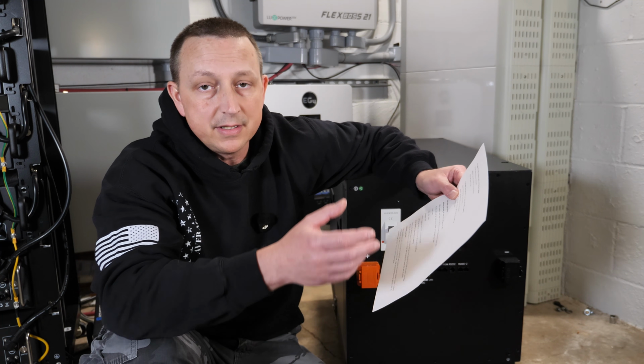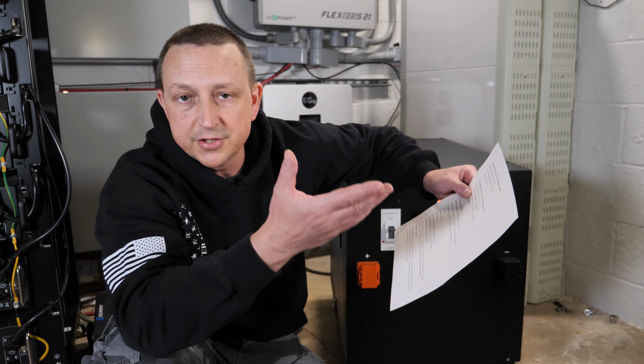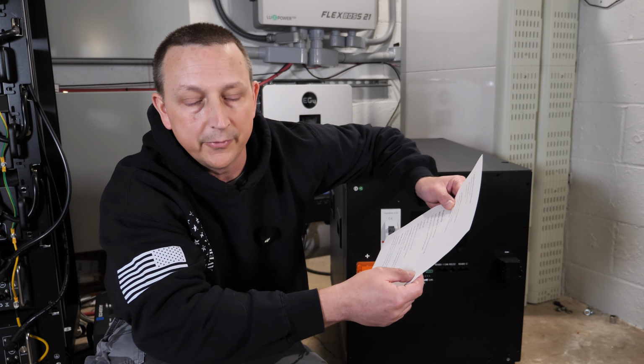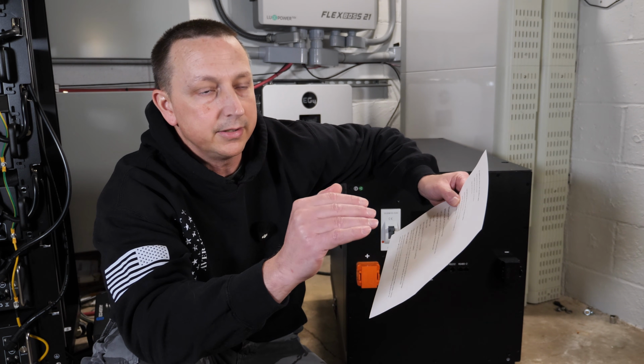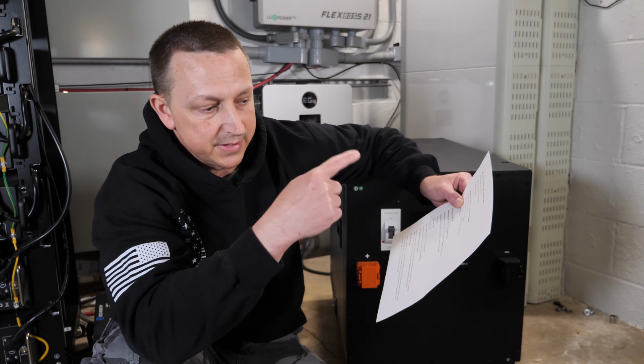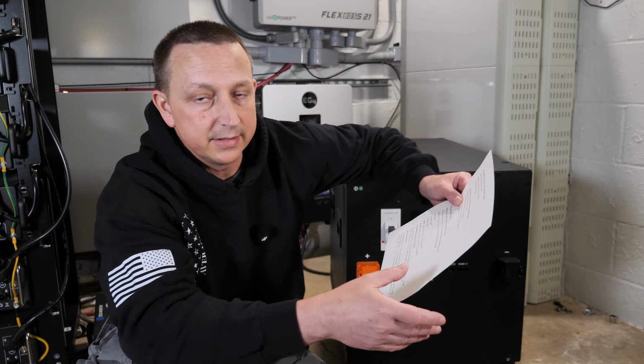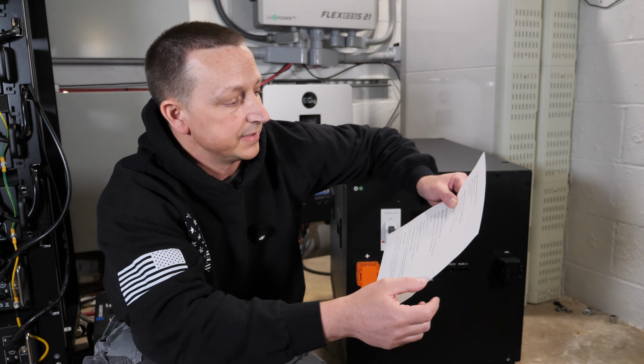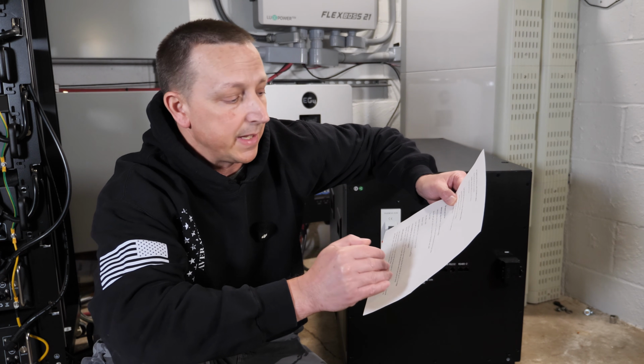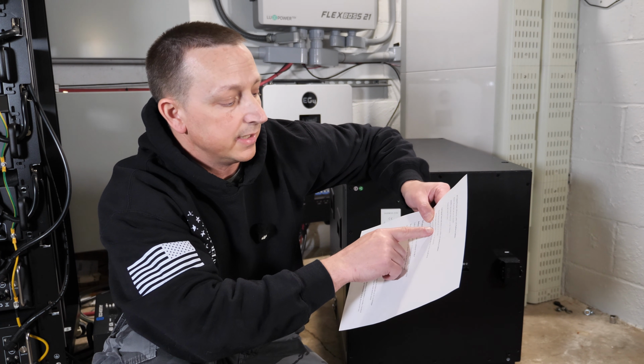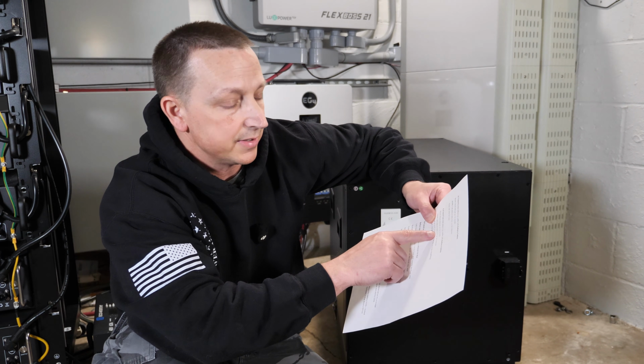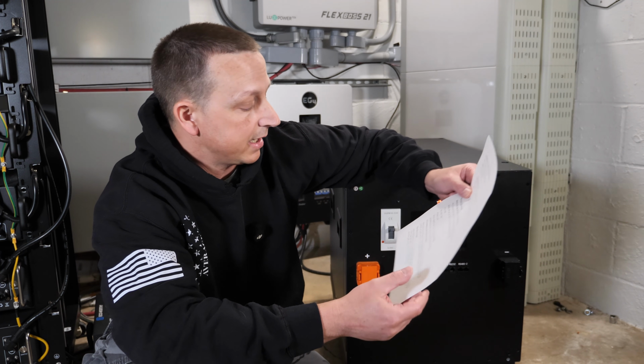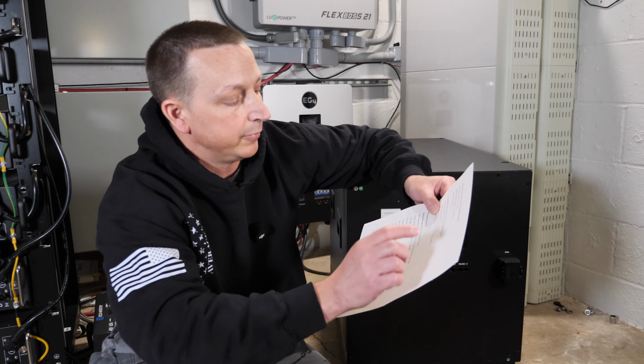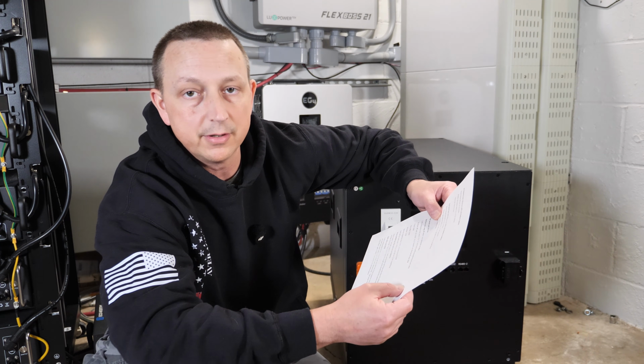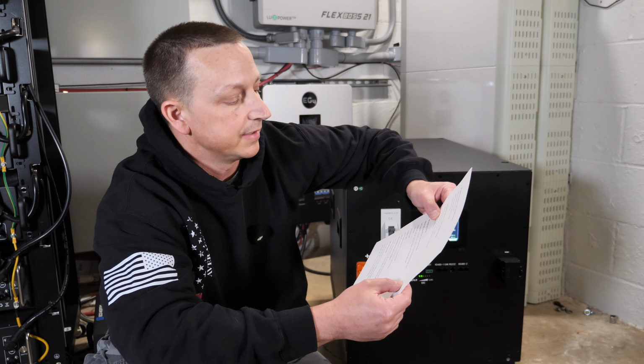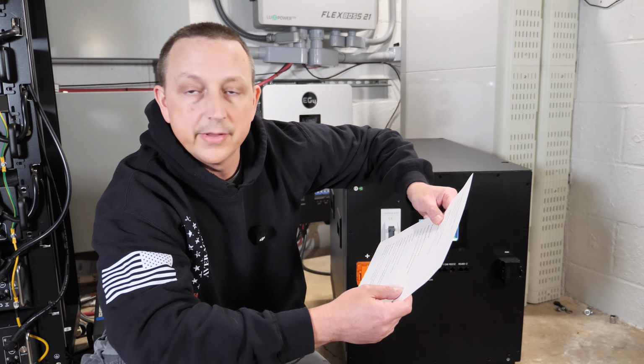For this one, I showed it earlier on screen how I came up with it, but I took the calculated battery capacity, which was technically both tests, and I subtracted the previous test, which was 660.6, from that entire total, and I got 668.6 amp hours. So then I did 668 times 51.2 volts nominal, and we got 34.20 kilowatt hour, which is 1 more kilowatt hour than previously.